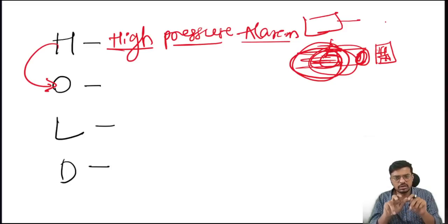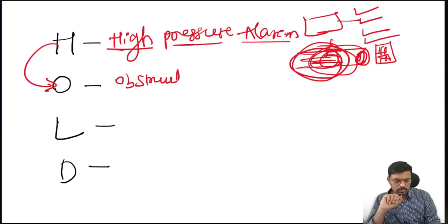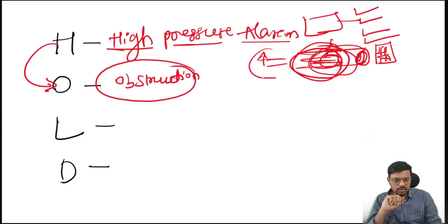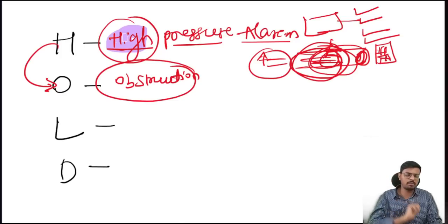When the tube kinks, when the tube blocks, when there is a secretion in the tube which completely blocks it, so again the overload of secretions, kinking of the tube, blocking of the tube, and biting of the tube, where the tube gets obstructed, the pressure inside the tube increases, which will deliver the high pressure alarm.